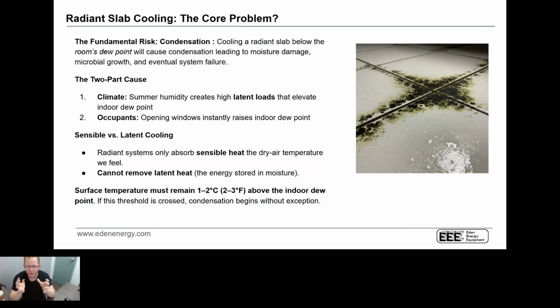What happens as the air conditioning is running less and less because the loads are getting smaller and smaller is you start to have an increase in humidity. So you'll see people like Gord Cook and Robert Bean, who are building science experts, love listening to them talk. And what they're advocating for is we need to treat sensible and latent cooling as separate loads that get handled differently. It's not that complicated, but we need to deal with it. So that's true whether it's an air to water or an air to air.